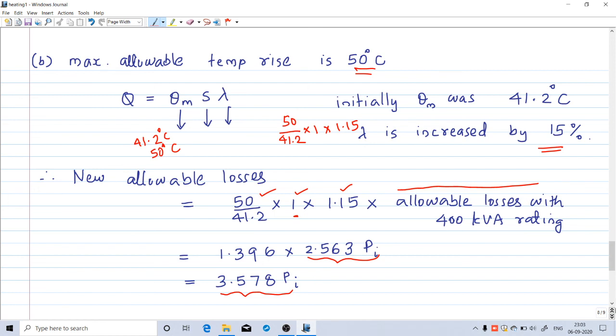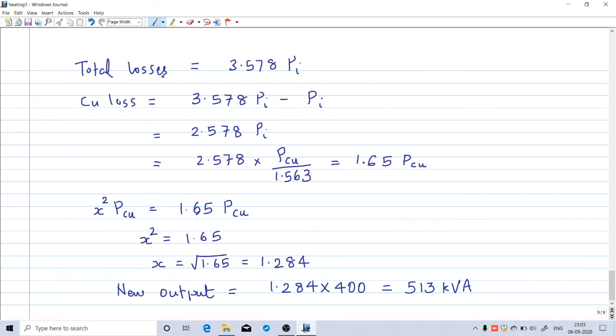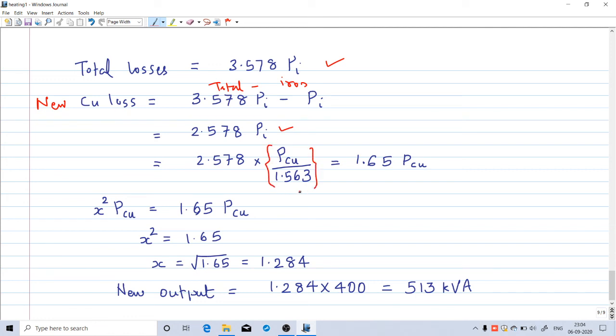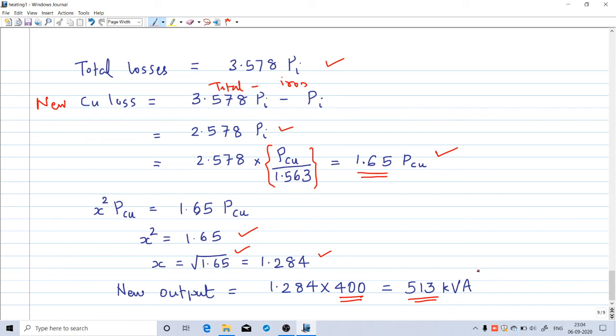Expressing in terms of copper losses: new copper losses equal total losses minus iron loss, which is 3.578 pi minus pi equals 2.578 pi. Since pi equals pcu / 1.563, new copper losses equal 2.578 times (pcu / 1.563) equals 1.65 pcu. Therefore x squared equals 1.65, so x equals the square root of 1.65, which is 1.284. The new output is 1.284 times 400 kVA, giving a new rating of 513 kVA.